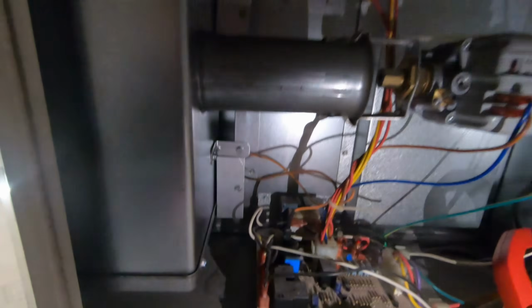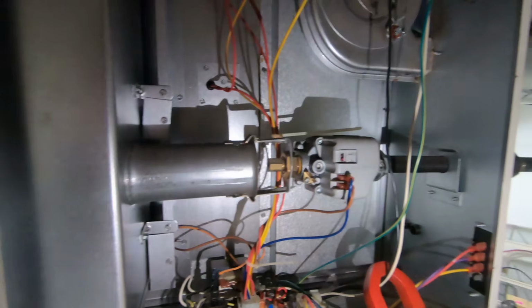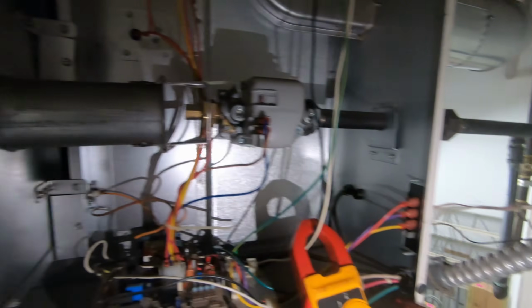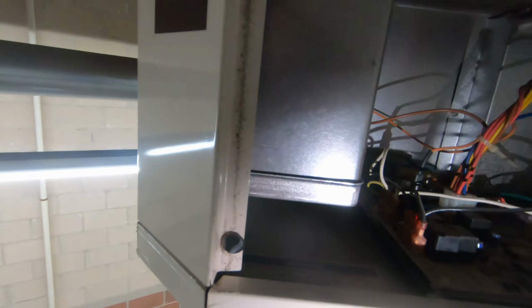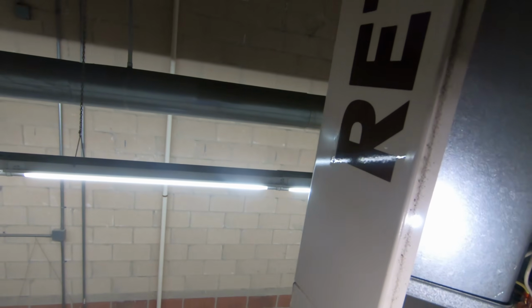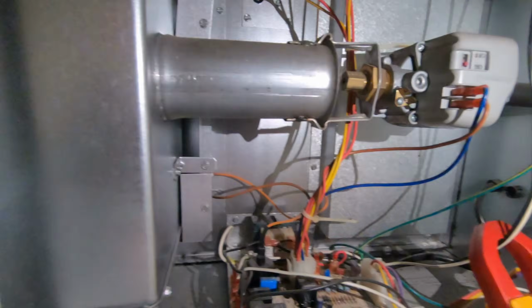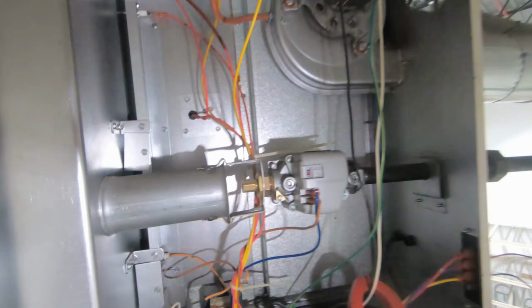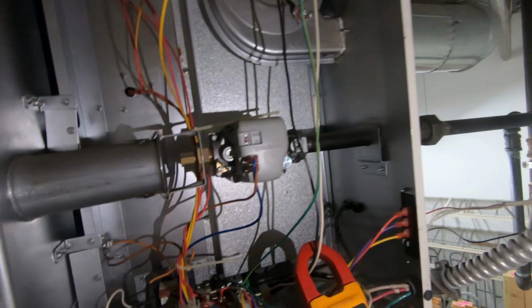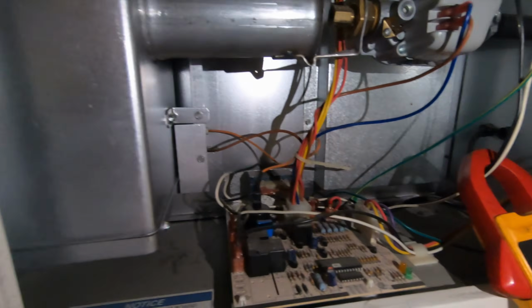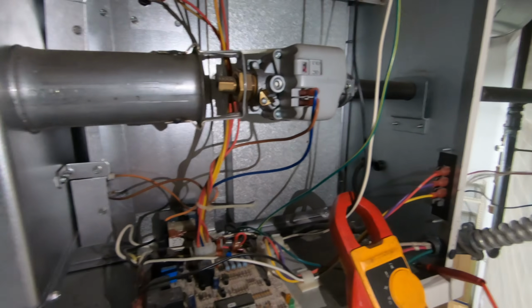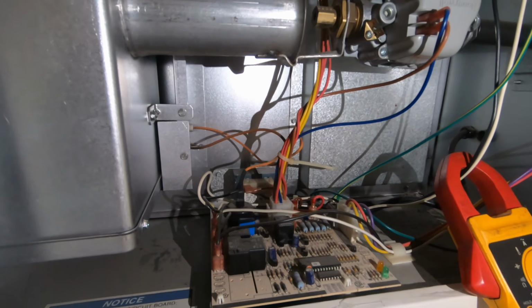Then I'm gonna try to get around to this side and inspect this heat exchanger, but I'm kind of in a precarious situation here. I would like to at least try to get a better look at that heat exchanger, because if it's cracked, well then might as well just plan to replace the unit. So let me move some things around - I'm going to jump out G, make sure that blower comes on, and we'll be back with you shortly.